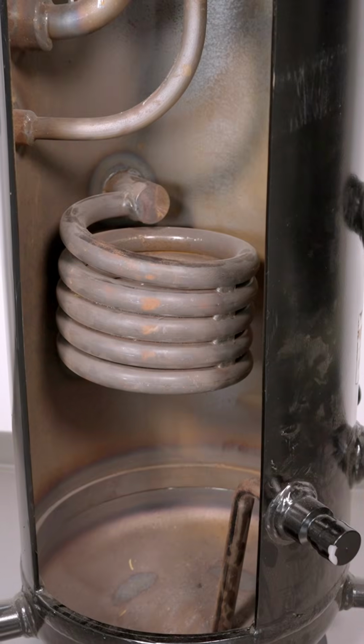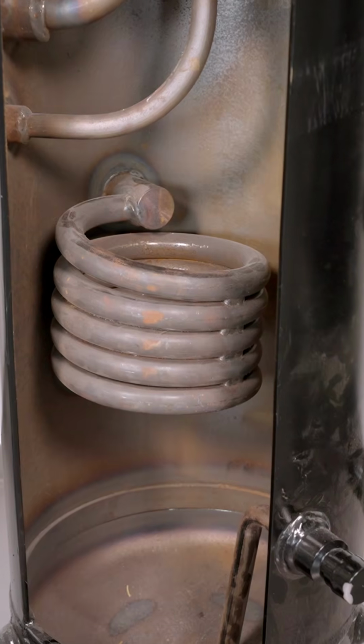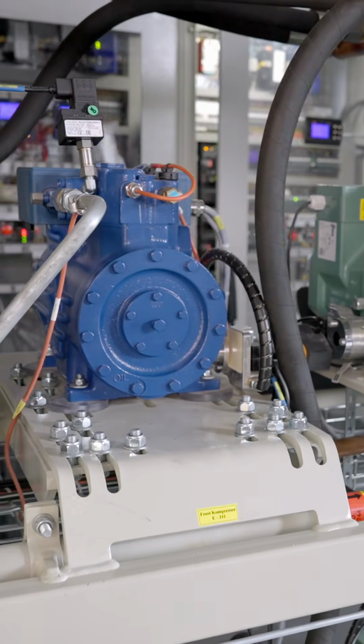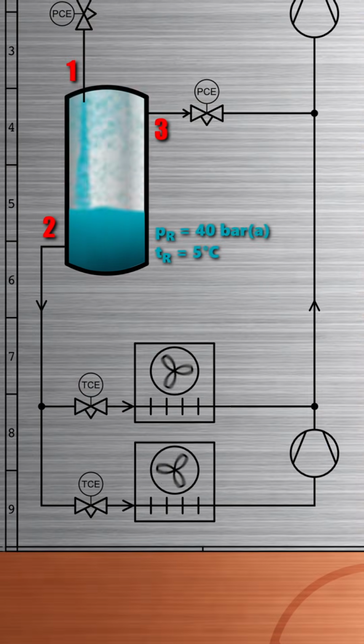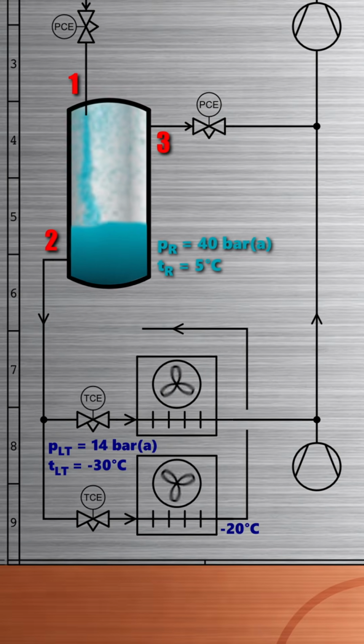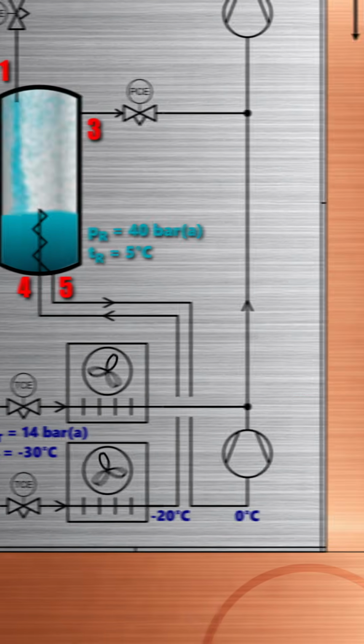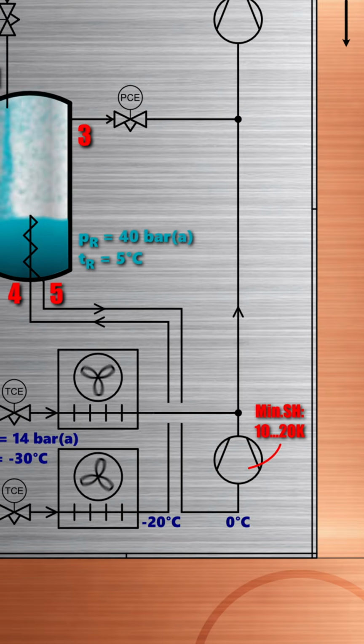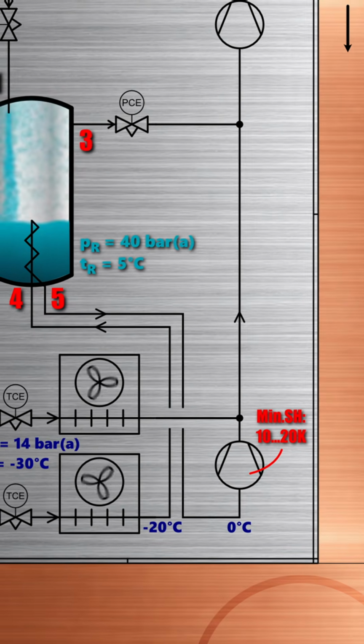The heat exchanger inside the receiver is responsible for the superheat at the low temperature compressors. Due to the constant receiver temperatures, the suction gas receives a safe and highly predictable superheat. A minimum superheat of 10 to 20 Kelvin is commonly recommended for CO2 compressors.